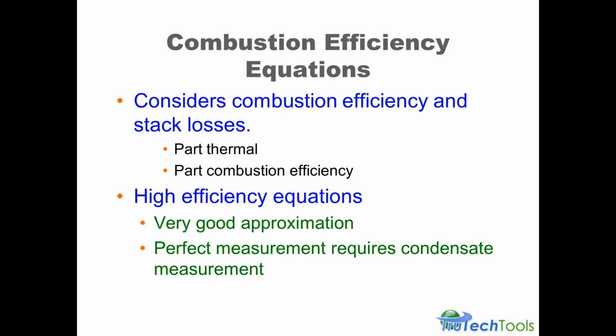The high efficiency equations, if you were to get a perfect measurement of high efficiency, if you remember we showed on the slide a couple of slides back, water vapor at perfect combustion is always there. If there was a way to measure water vapor and measure the condensate, you could tell exactly what the high efficiency numbers were if you're using a condensing system. However, that's not a really practical way of measuring. So the manufacturers have come up with very good approximations for what they call the high efficiency operating, or that's for condensing furnaces or condensing boilers, to be able to use just the temperature and oxygen and tell you what the steady state operating efficiency is for the appliance.